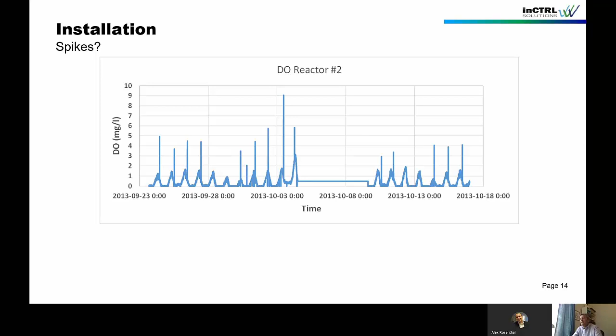Another thing a lot of people will have seen: that's a DO probe, and you see these spikes. And you see it's quite regular. That's what you want to look for, so check for regular patterns. In this case it's actually cleaning. The spikes mean that you cleaned, so that's auto cleaning using pressurized air, and you switch back to normal operation too soon. So what you're measuring are these high concentrations due to the cleaning cycle.